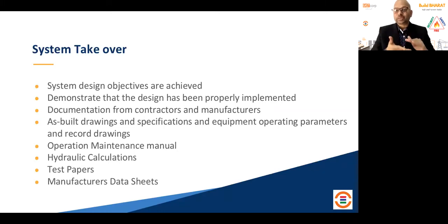But if you don't have the test paper, if you don't have that documentation, or if you don't ask for it from the OEM during the commissioning stage, and you take over the system assuming it is 2-hour rated just because it says so in the purchase order, then that's a mistake.